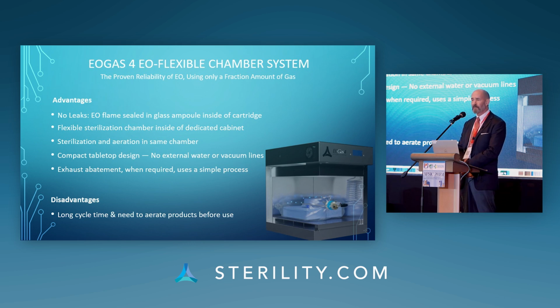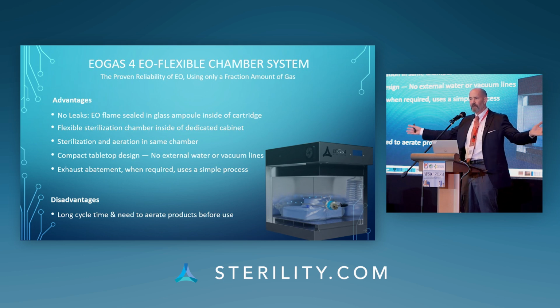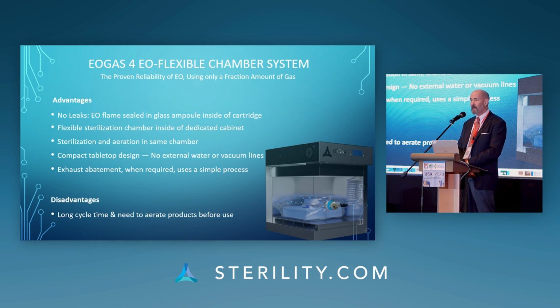This is a very compact tabletop design. We've got one out in the lobby that we can show you, but this is very different from the very big, bulky ethylene oxide systems that many of you may be familiar with. Sterilization and aeration are taking place in the same cabinet. The operator is never going to be unloading the sterilizer or coming in contact with products until they're fully aerated. And lastly, because we're using such a small amount of gas, emissions abatement tends to be quite easy and relatively inexpensive compared to other systems.